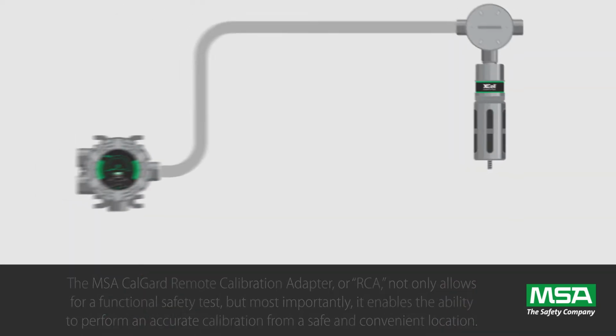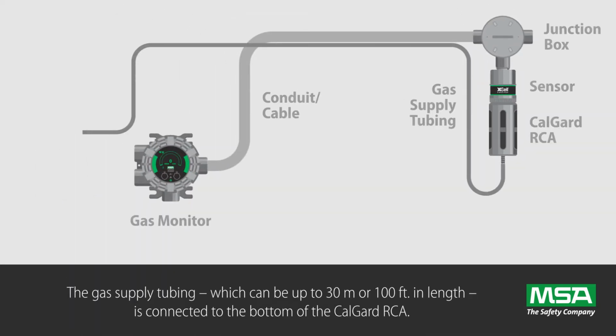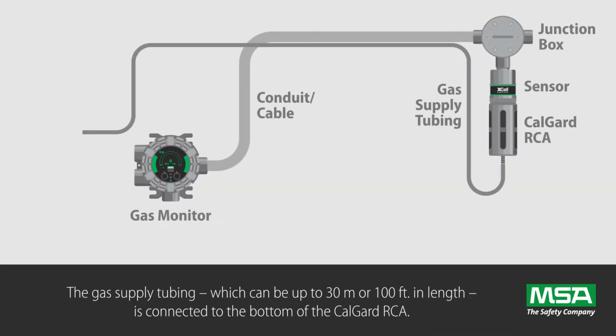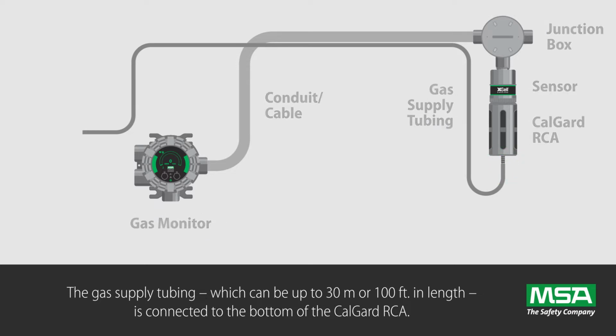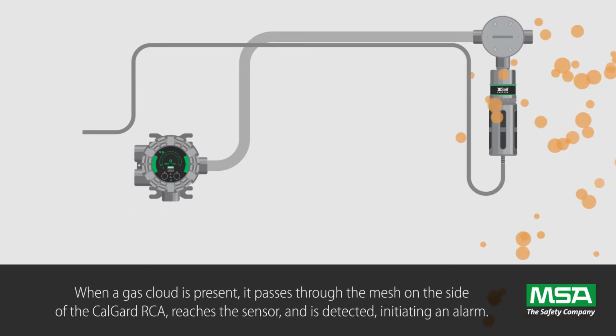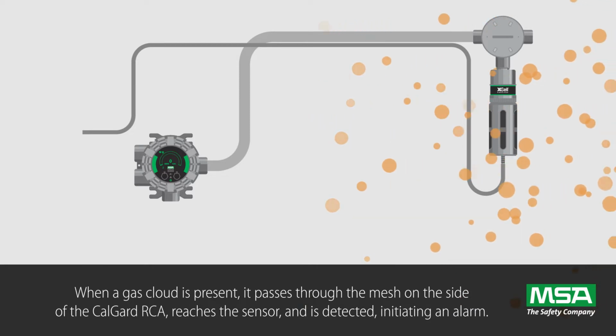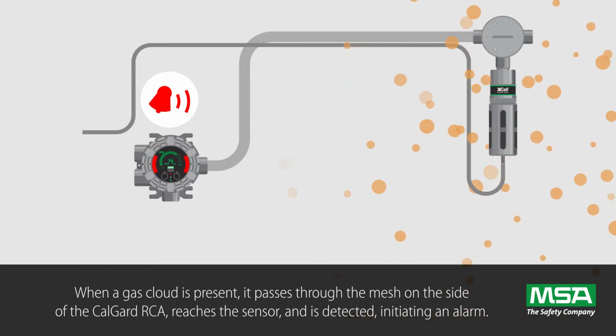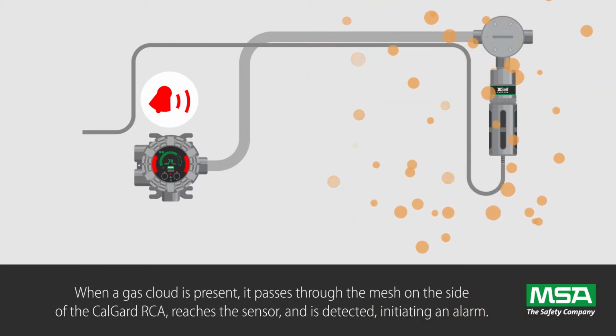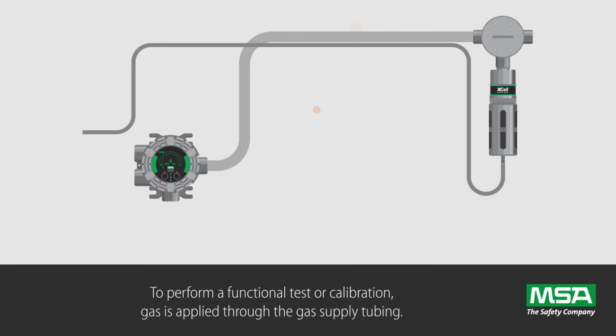The gas supply tubing, which can be up to 30 meters or 100 feet in length, is connected to the bottom of the CalGard RCA. When a gas cloud is present, it passes through the mesh on the side of the CalGard RCA, reaches the sensor, and is detected, initiating an alarm. To perform a functional test or calibration, gas is applied through the gas supply tubing.